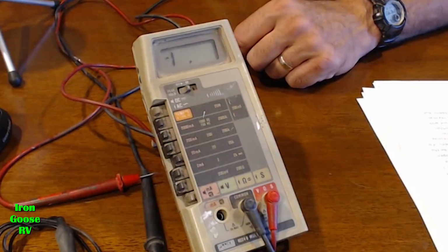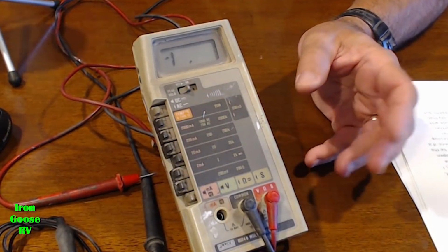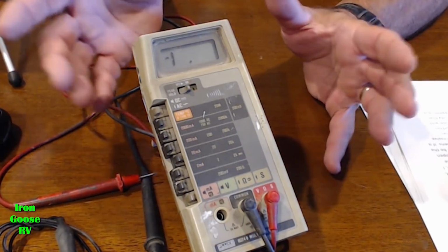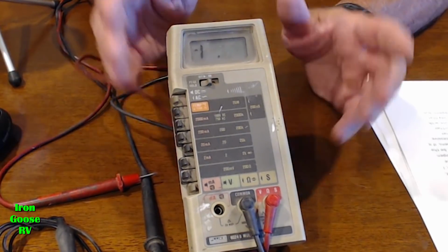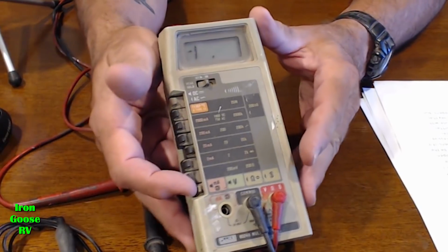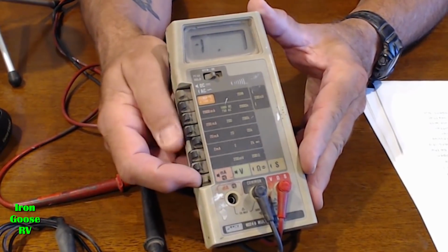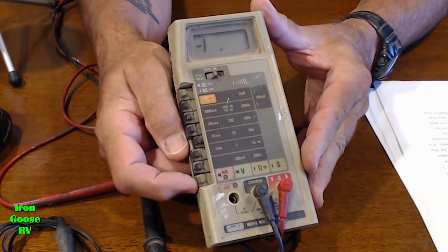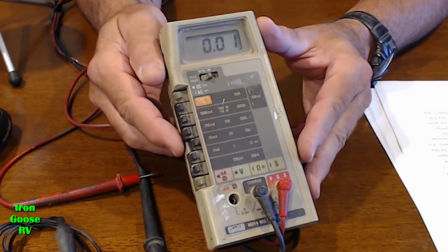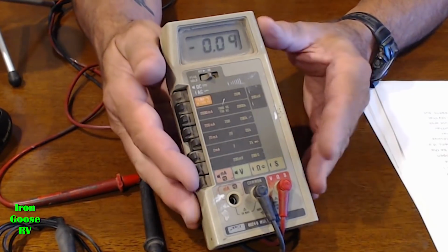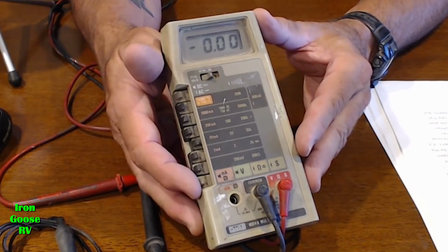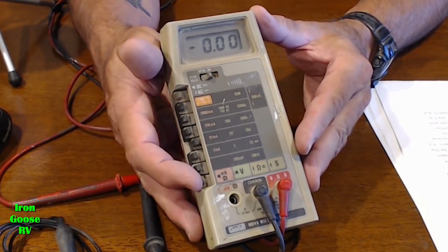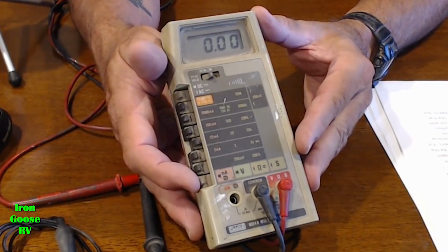One final thing before we close, and this is important if you value your tools like I do. If your DVM or voltmeter is still set to the resistance scale after you check for continuity or resistance, make sure as soon as you're done you take it out of that resistance mode by going back to a voltage mode. The reason for that is if you try to check voltage or current while it's still in resistance mode, you could damage your meter.